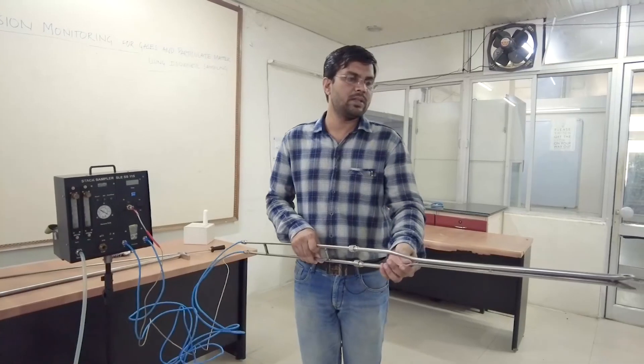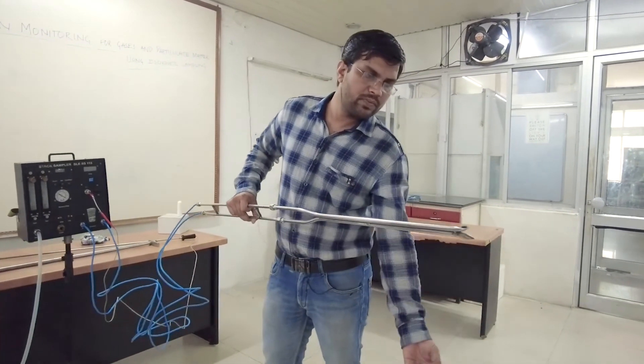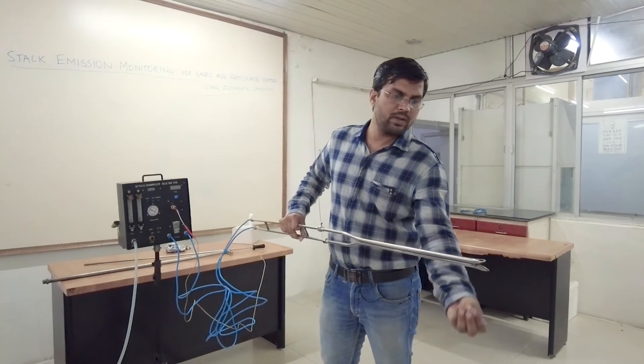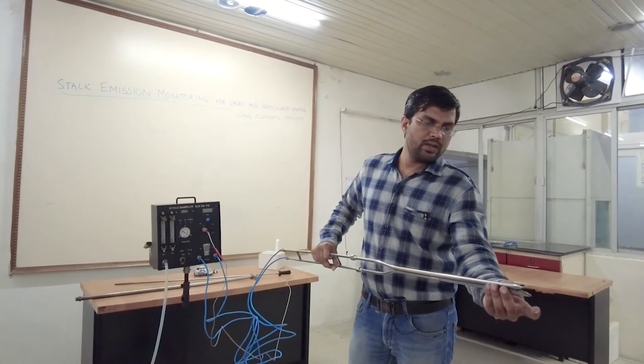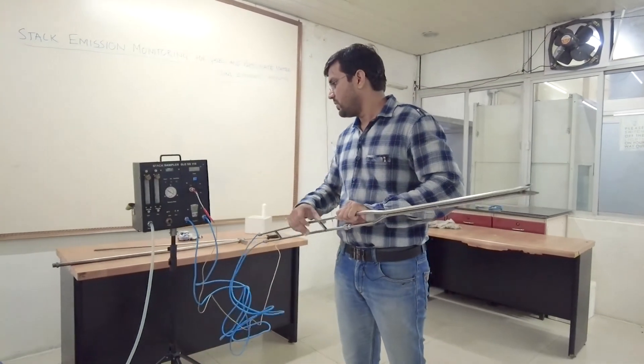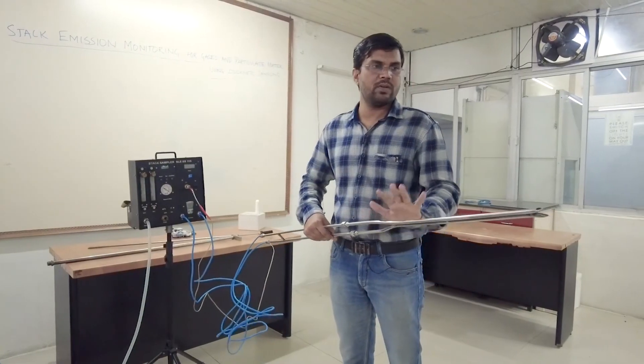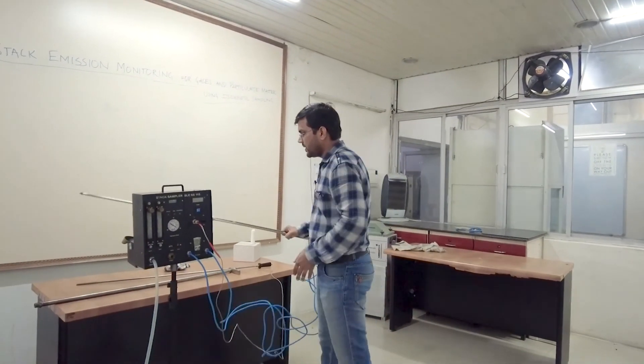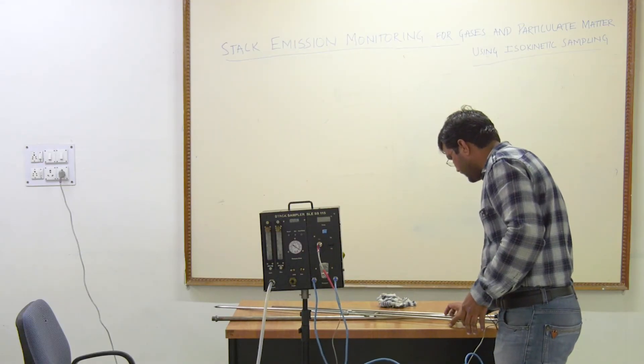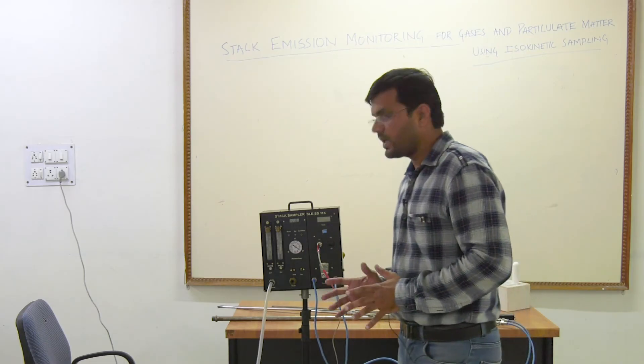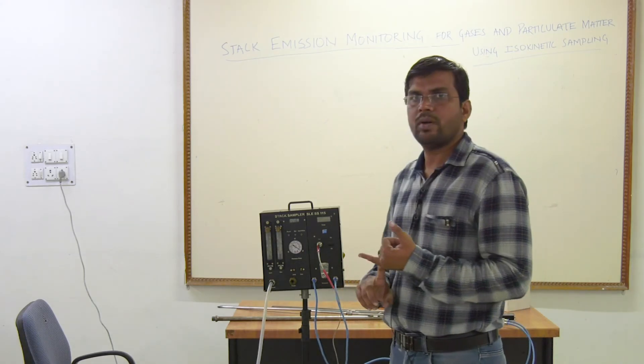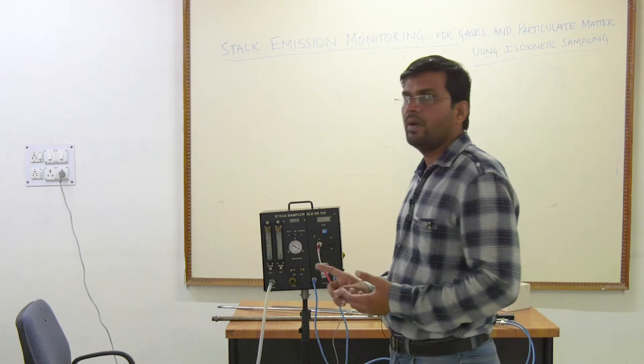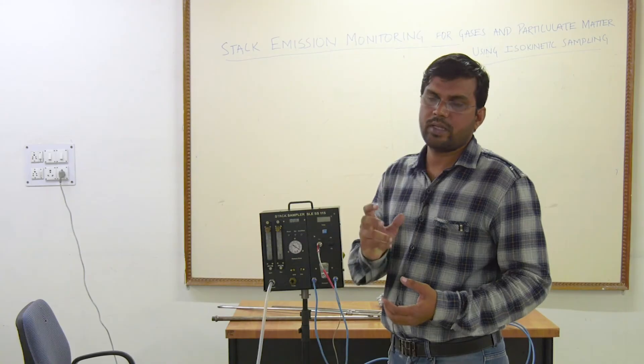The purpose of the two pipes on the pitot tube: when keeping this pitot tube oriented so that gas flows from bottom to top, there will be a pressure difference between the two probes — the velocity at the upper side will be higher and at the lower side lower. The difference between these two gives a reading, and using the fundamental equation of the pitot tube we can measure the velocity from the pressure drop. Temperature inside the stack as well as outside can also be measured using the thermocouple probe.